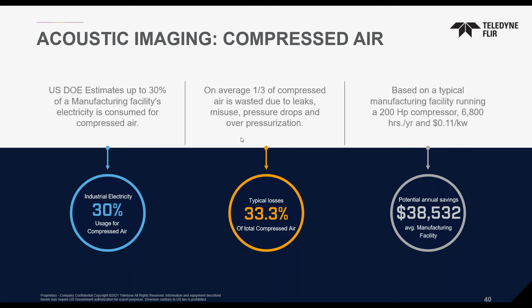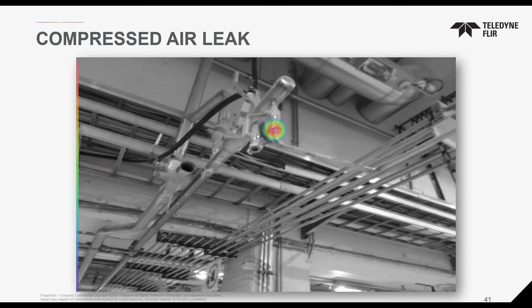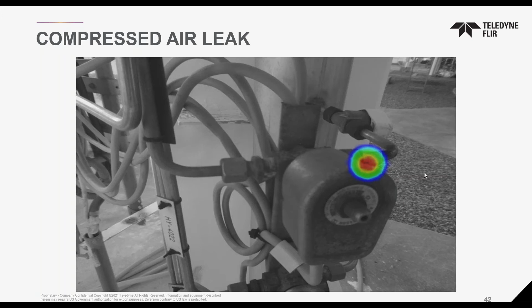So here are a couple of real images from our SI-124. It's a black and white image, and then you have this rainbow circle. That rainbow circle is where the leak is coming from. The unit, and we have a couple images of it as well, is a handheld unit, one-handed use. It's got a nice big display screen. All you do is take this unit, which runs on a battery, and walk around your facility. You can track from your compressor all the way to the station where that air is going. And you can track your pipes and tubings and see if there are any leaks.